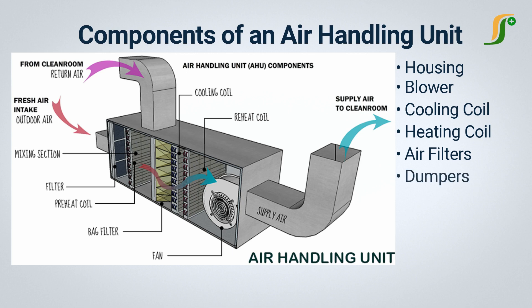Dampers are barriers between the air supply and are used to control the airflow in the air handling unit. They are used to regulate the supply air and return ducts in air handling units. Ducts are insulated metal piping from the AHU to the manufacturing area. Two different ducts are used for air supply and return. Insulation minimizes the effect of the environment on the supply and return of air, helping to minimize energy loss. The condensate drain collects water droplets from the coils in a drain pan, and a drain line carries the water from the drain pan to outside the housing.